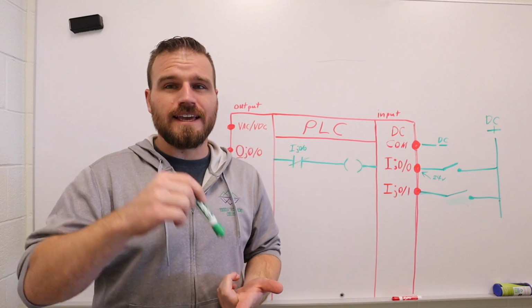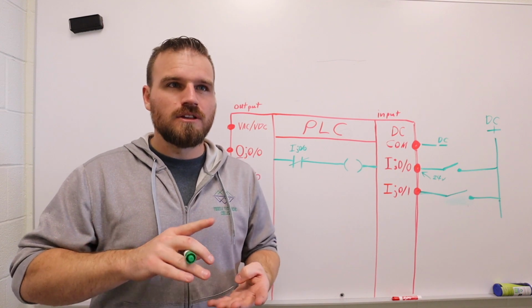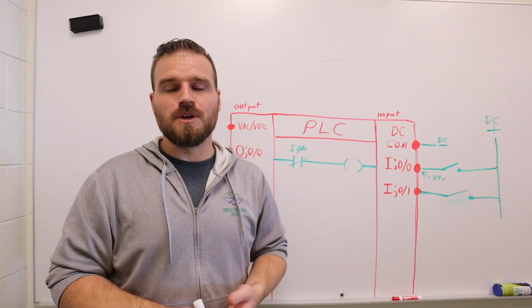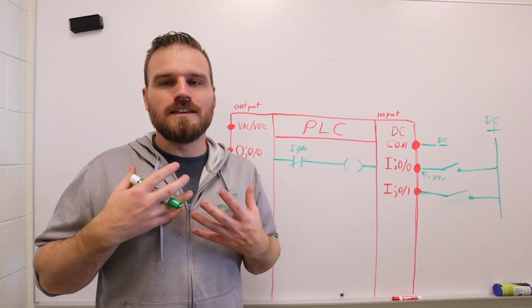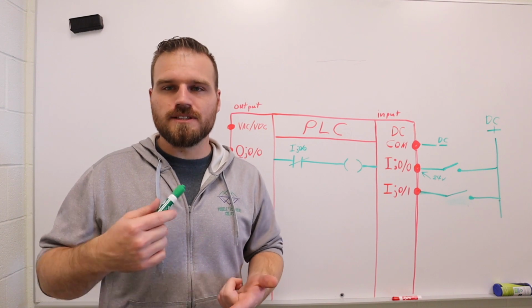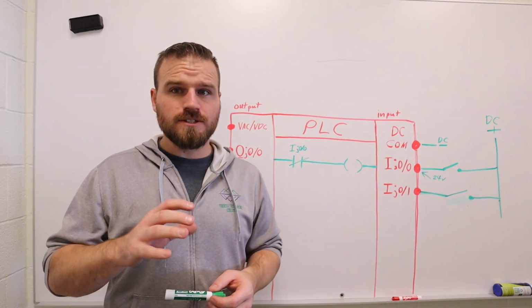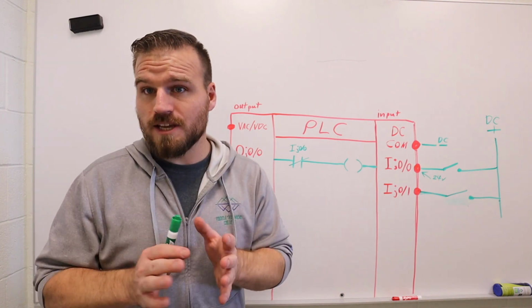So it's going to be things like lights, relays, maybe some buzzers, things like that, some pretty low voltage type things. We're going to be sending it out, okay? Most of the time it's going to be coils. It almost never will be anything that's high amperage. Usually things like coils on a hydraulic valve are too high. They don't seem to be loved by PLCs. Not saying you can't do it.